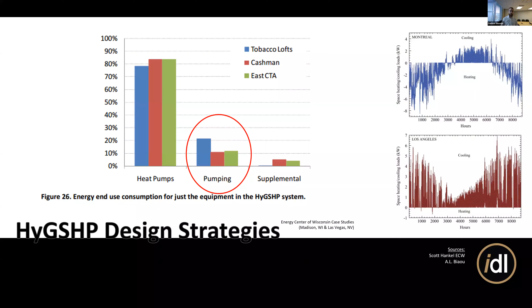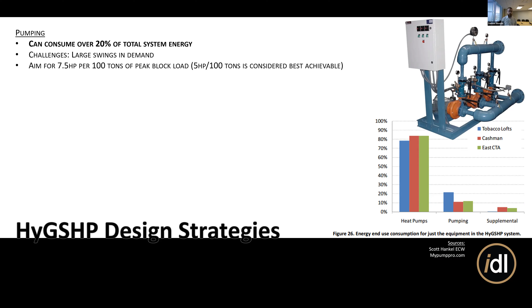It can be 20% or more, depending on the design of the system, of how much energy is being used there. So one aim is to make sure that you've got about 7.5 horsepower pumps per 100 tons of peak block load. Instead of worrying about very large swings in demand, switching it back and forth very, very quickly, really try instead to run it slowly, seasonally, have it be the tortoise, and then have your supplemental system kick in if you have to reach those extra peaks.